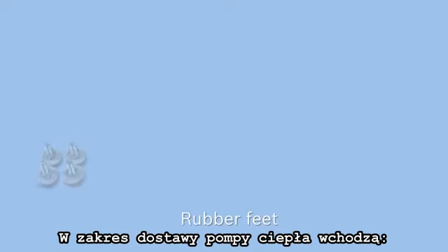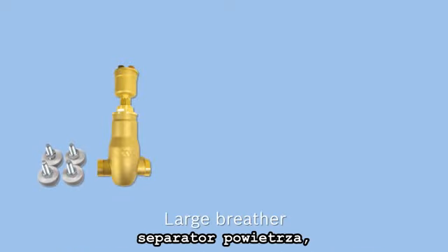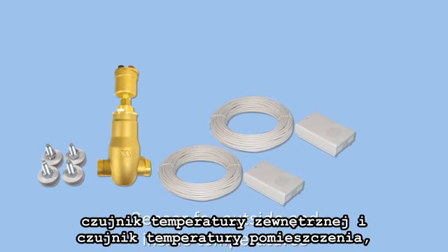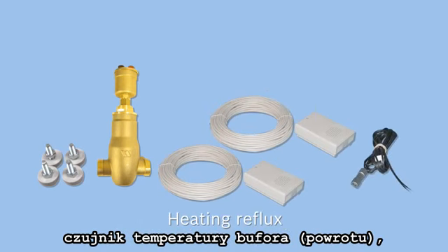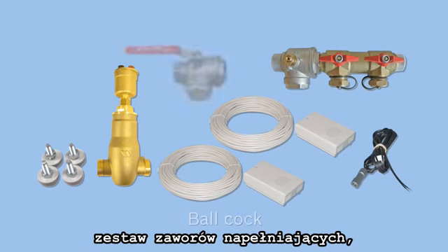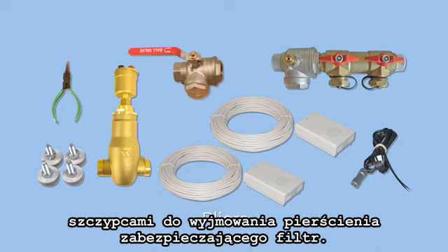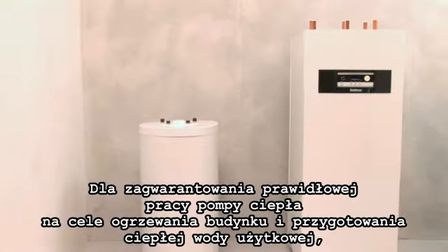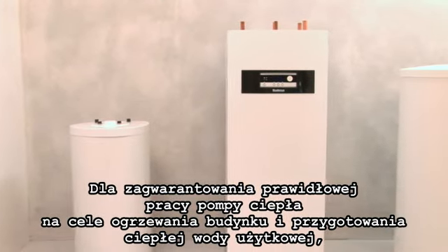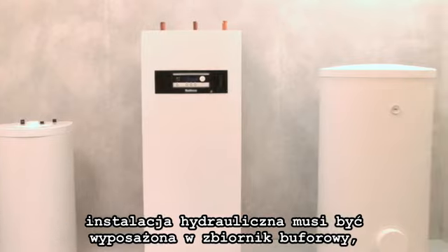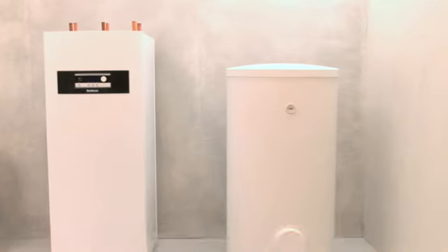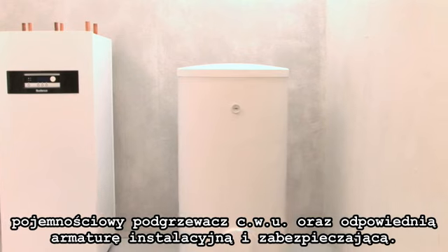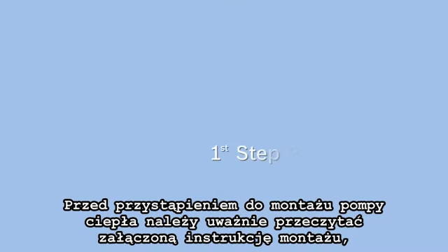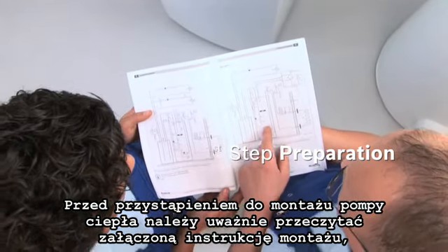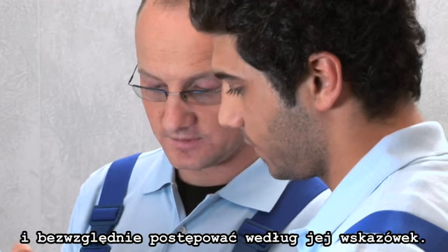The scope of delivery includes rubber feet, a large breather, a sensor for outside and inside temperatures and heating reflux, as well as the filling and rinsing station, including a ball cock with contamination filter and pliers. In order to guarantee high operational safety, the system shown here is also equipped with a hot water tank and appropriate fittings in addition to a buffer storage. Before starting the installation, please carefully read the enclosed installation instructions and follow them.